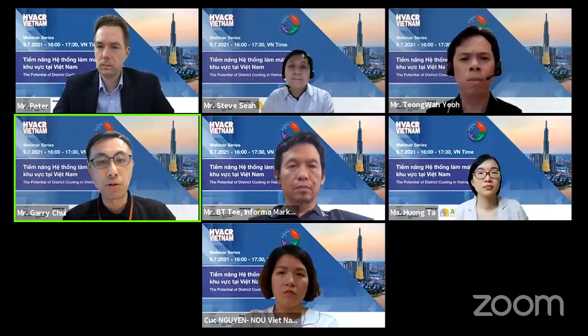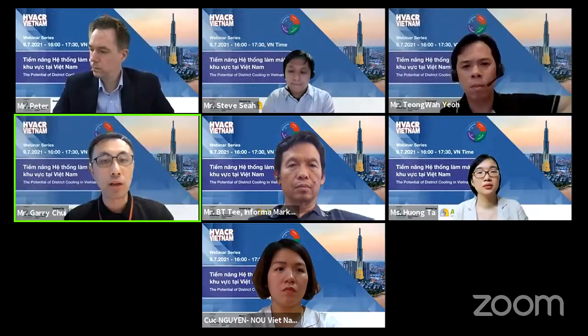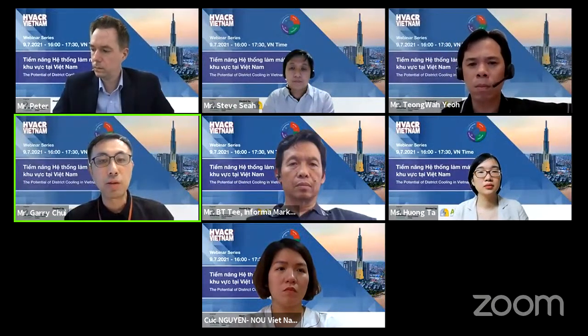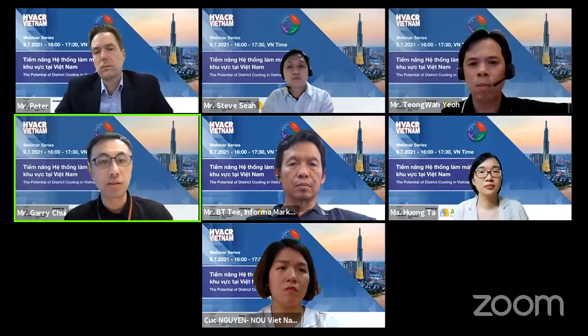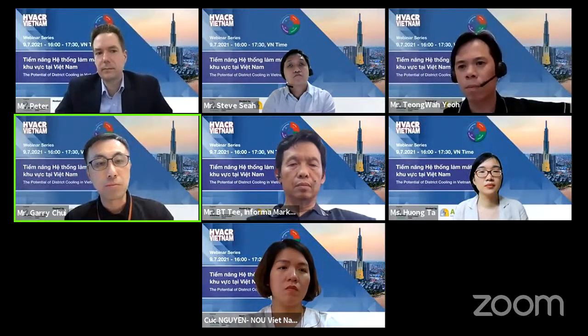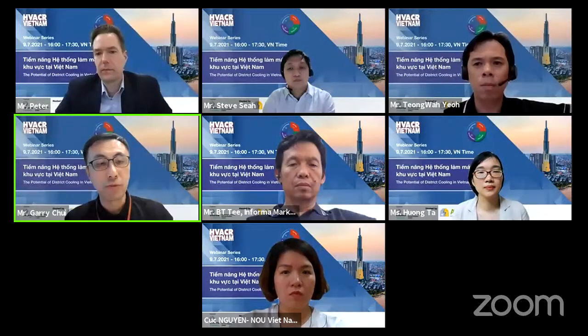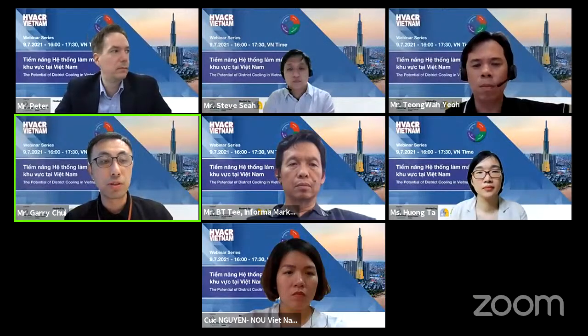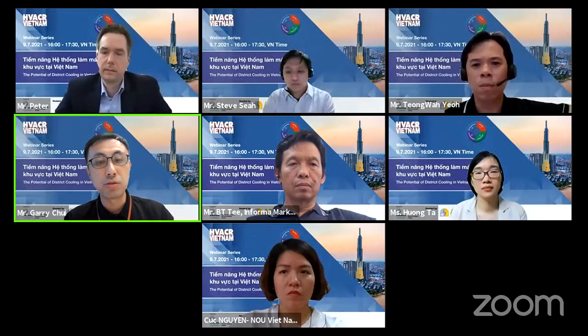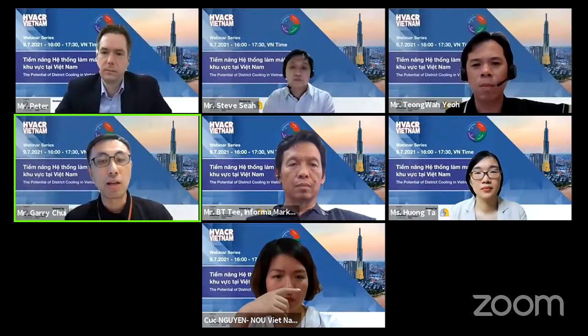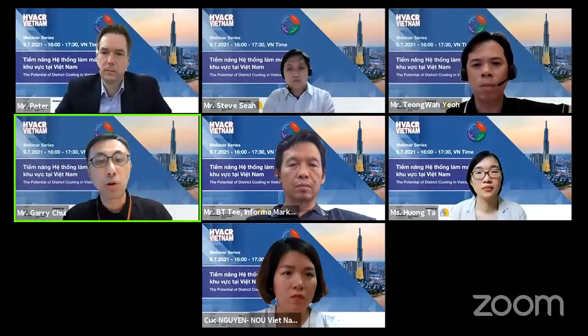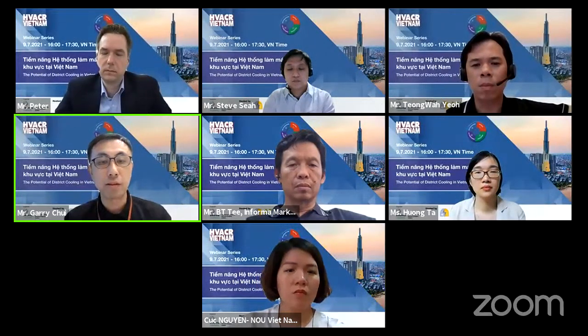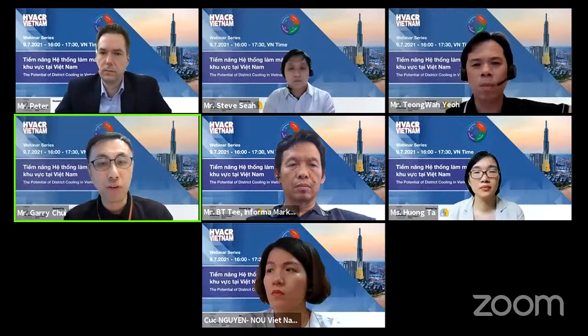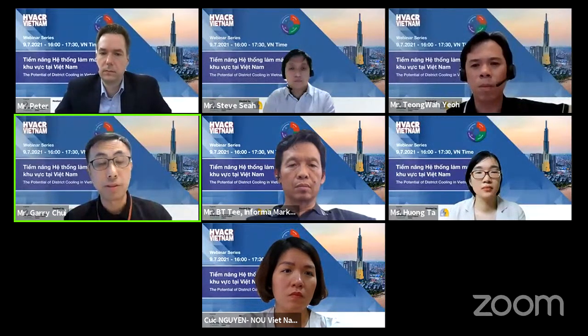For example, in Singapore we're already seeing that many buildings, traditionally designed systems with a golden rule of 7 degrees C chill water temperature. But if you look at what Singapore designers are using today, through optimization of the air terminal devices, the chill water temperature they're designing for now is like 8.5 or even as high as 9 degrees C.